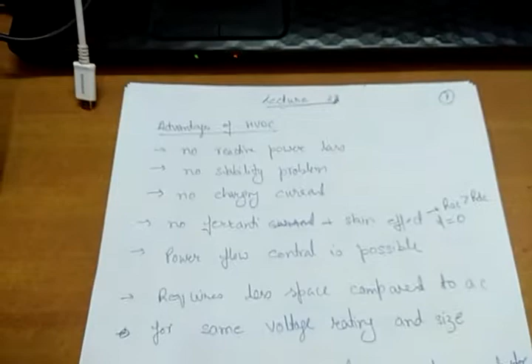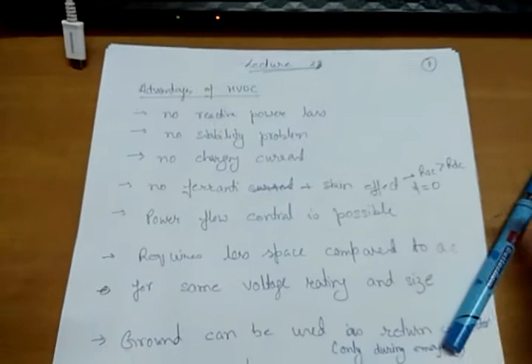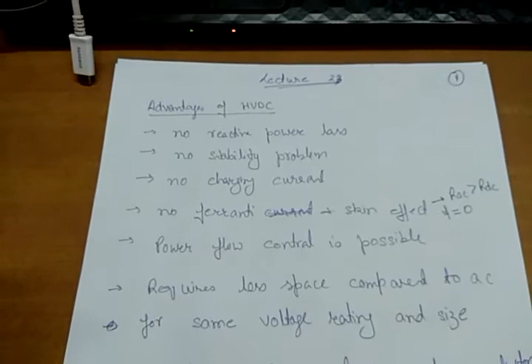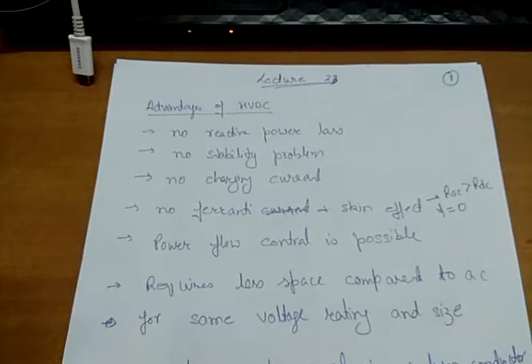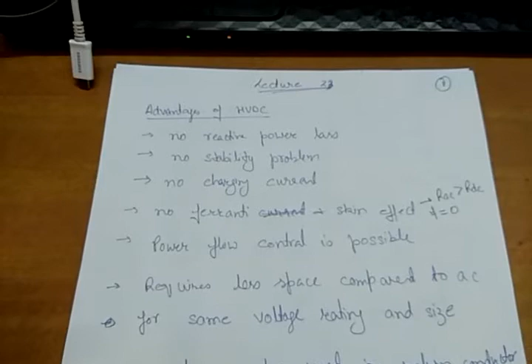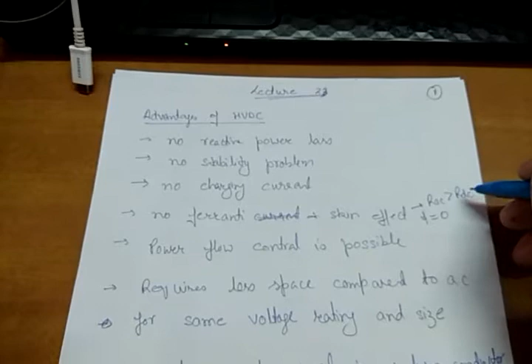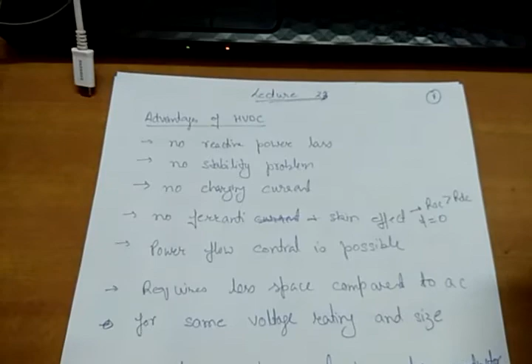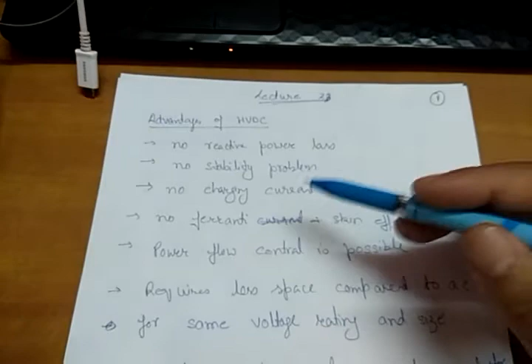Then no charging current. There is no capacitance between the conductor and the ground in case of a DC, so no charging current attached. Then no Ferranti and skin effect. Skin effect, you know what is skin effect. In case of AC, the current has a tendency to flow through the outer strands of the conductor, and the current through the inner strands of the conductor is zero. That is why we say resistance of AC is greater than resistance of DC. Why? Because the frequency in DC is zero, and this resistance depends upon frequency as well. So in DC there is no skin effect, and no Ferranti effect.